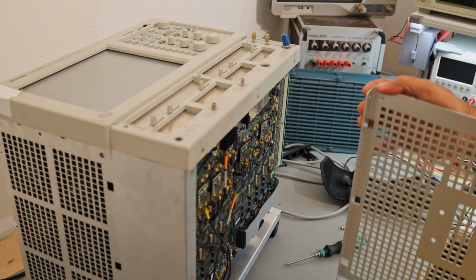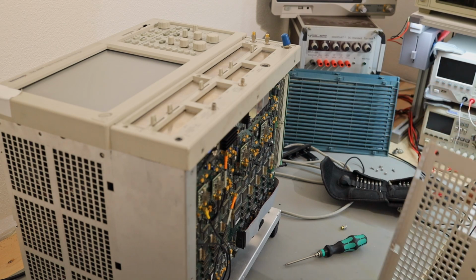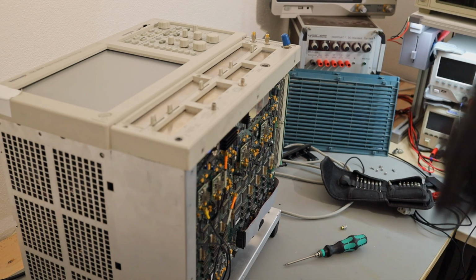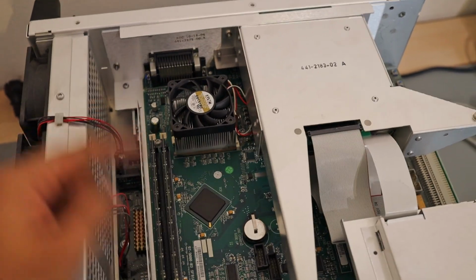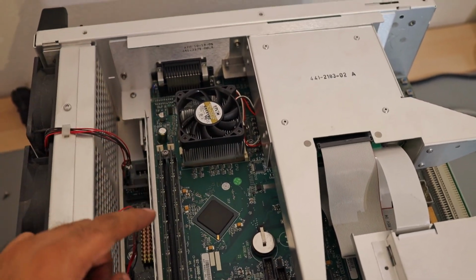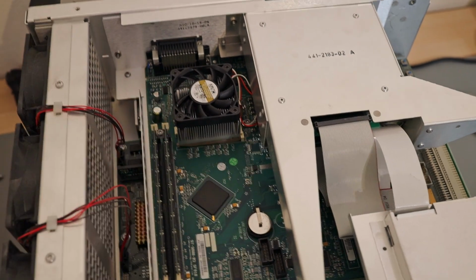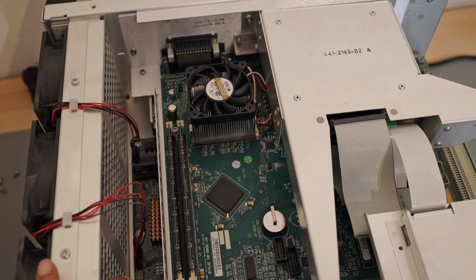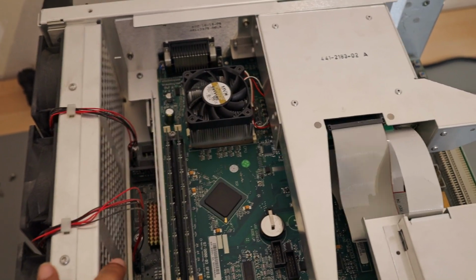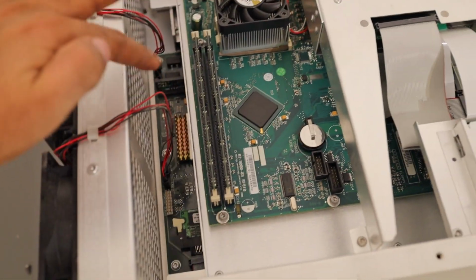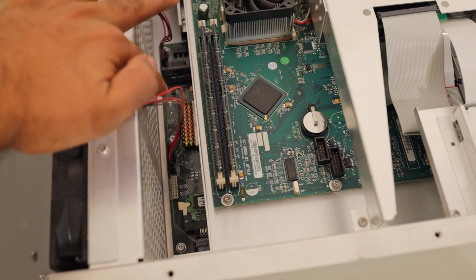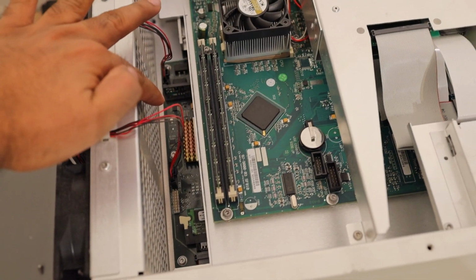One of the side panels is out. I believe we don't need to take both of the side panels out, because the thing which you see in front of you, this primary board, is a normal Intel motherboard, Intel CPU Celeron is under there. This is the 256, total 512 megabytes of RAM. The board on the bottom which you see, this is the primary board which runs VxWorks operating system.